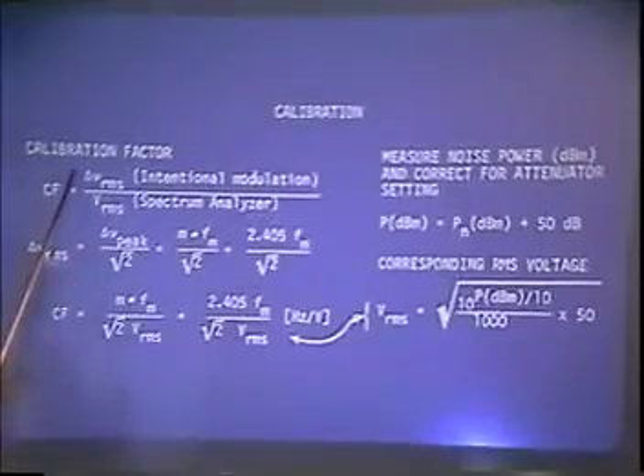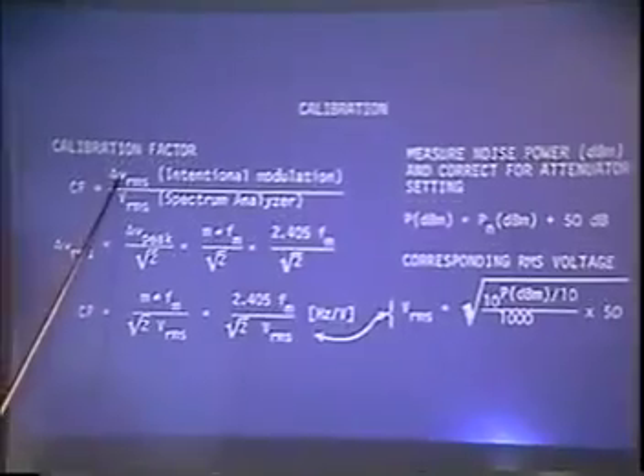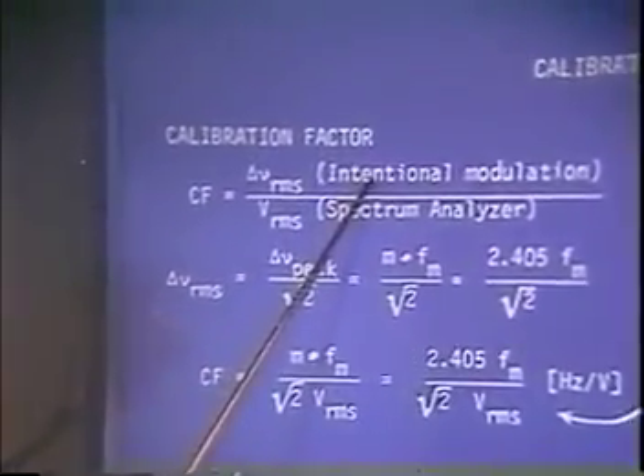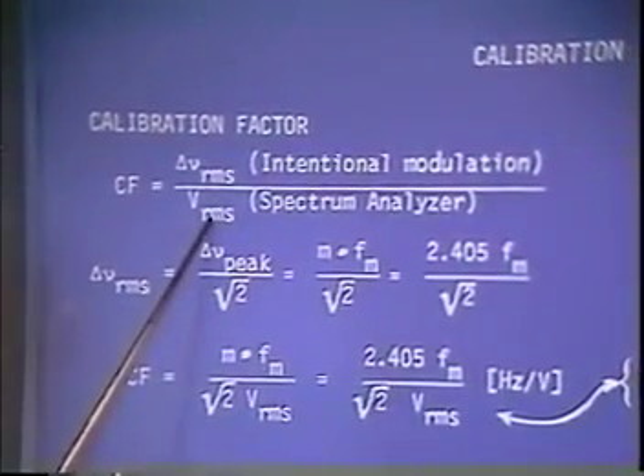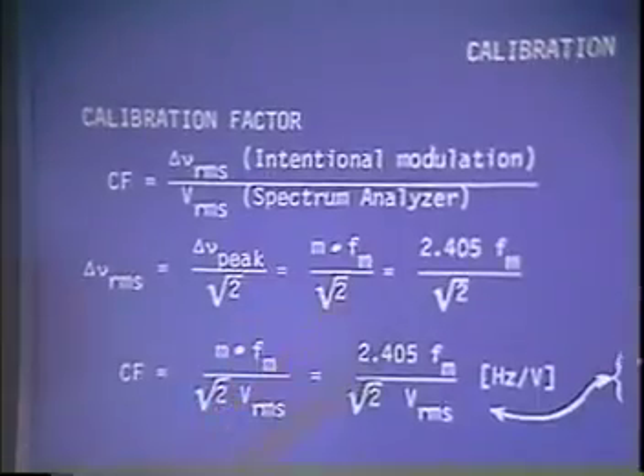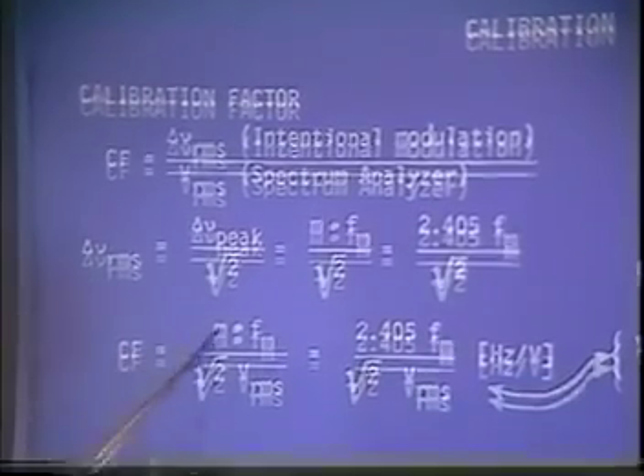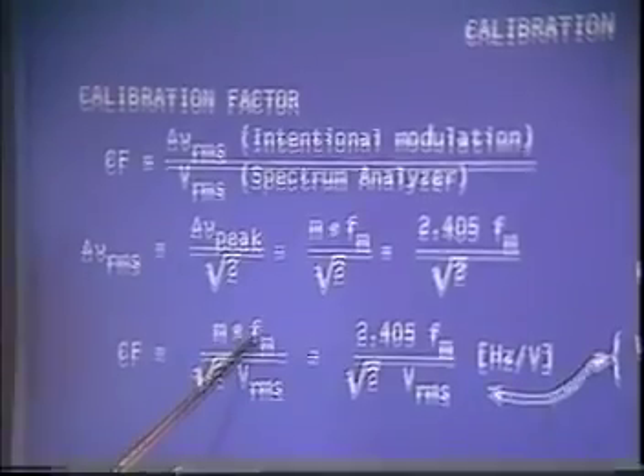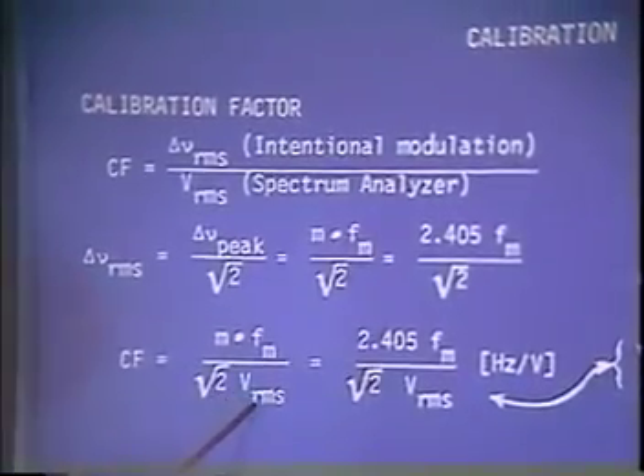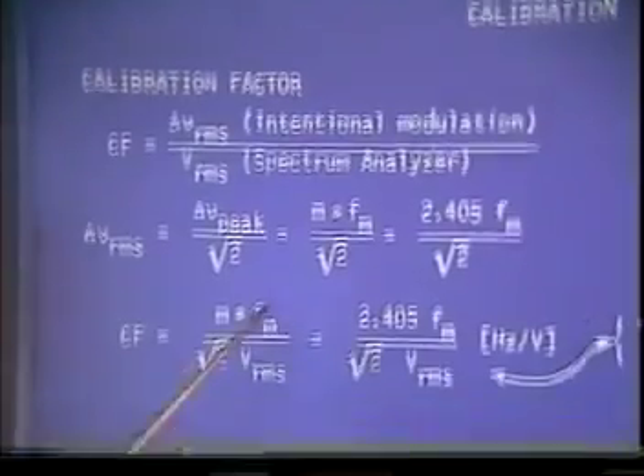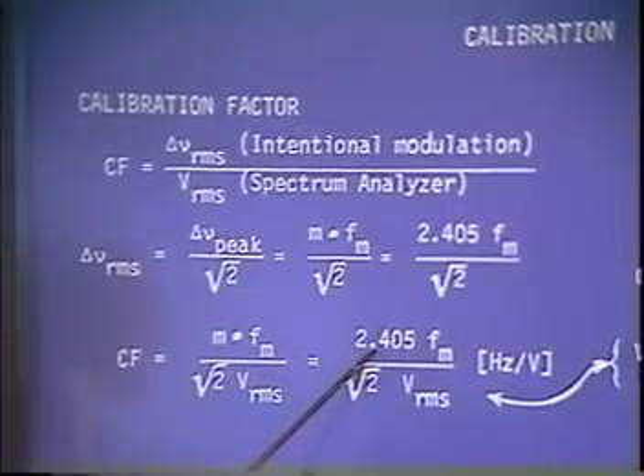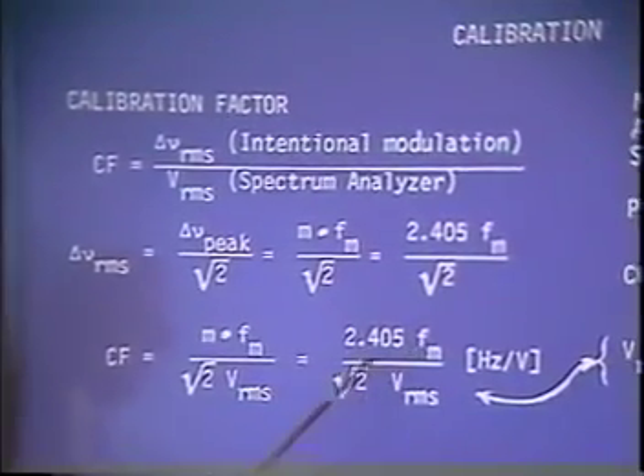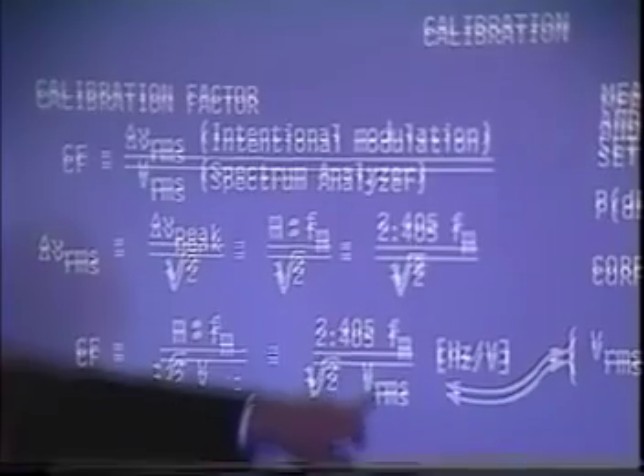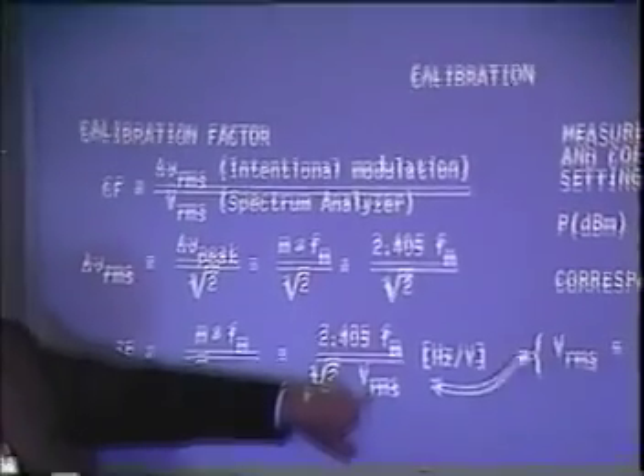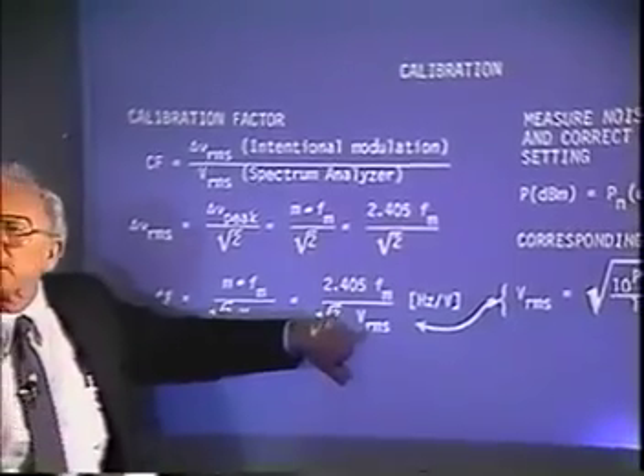Now let's look at this then in the system. The calibration factor: you're going to get a variation of the voltage by intentional modulation, and you're going to measure the voltage. Now, the way you do this is, the calibration factor is the modulation index times F sub m, the modulation frequency, divided by the square root of 2 times the VRMS. Okay? Now, in our case, we said we'll modulate this to first Bessel null, 2.405 times F sub m, over square root of 2 times VRMS. Now, how do you get VRMS? That's the RMS voltage that you're reading at the output in the system. Well, you're going to measure it with a spectrum analyzer.